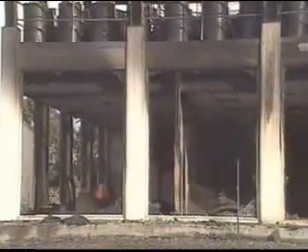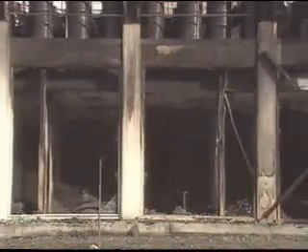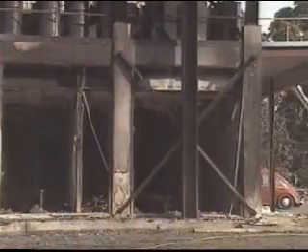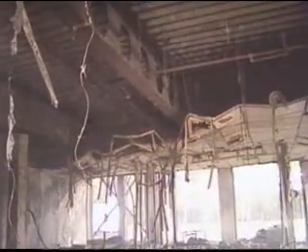There were no signs of distress or damage to the structure of the building during the fire. The structural steel members and the floor slab suffered no permanent damage. The extra light hazard sprinkler system was effective in controlling the developing as well as the well-developed fires in both the open plan and the small office areas.